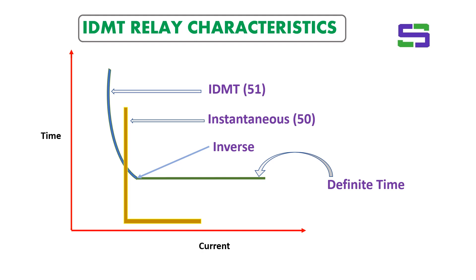The instantaneous element, in combination with the 51 and 50 elements together, will protect a specific zone. The left-hand side and lower-hand side zone is protected by the 51 and 50 elements of the IDMT relay. This is the basic concept of any IDMT relay for protection coordination in an electrical power system network.